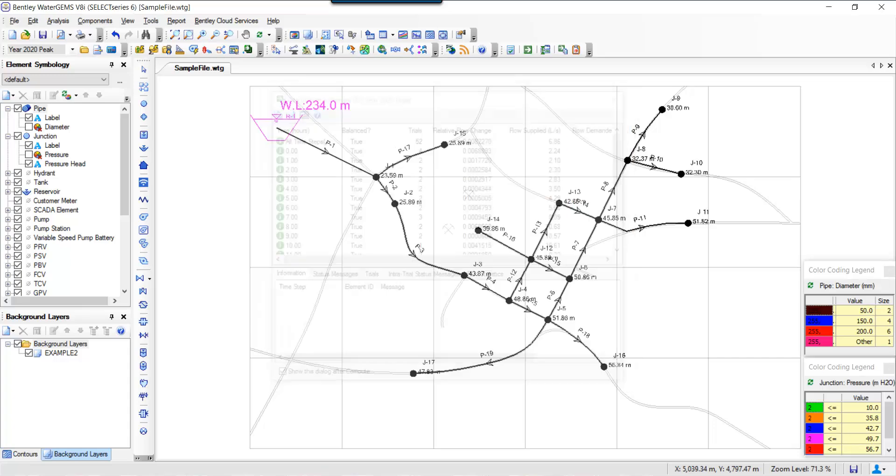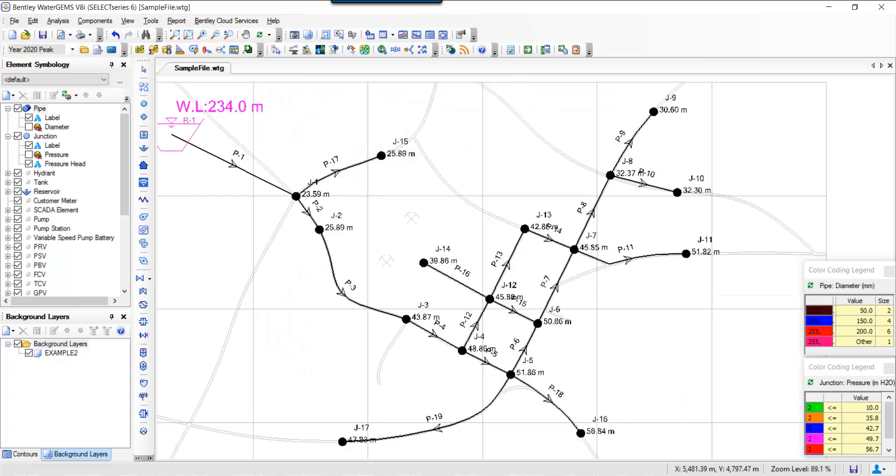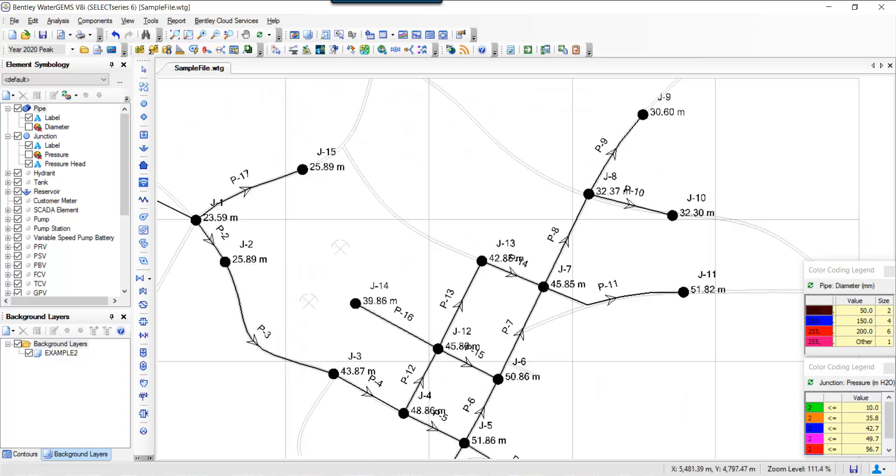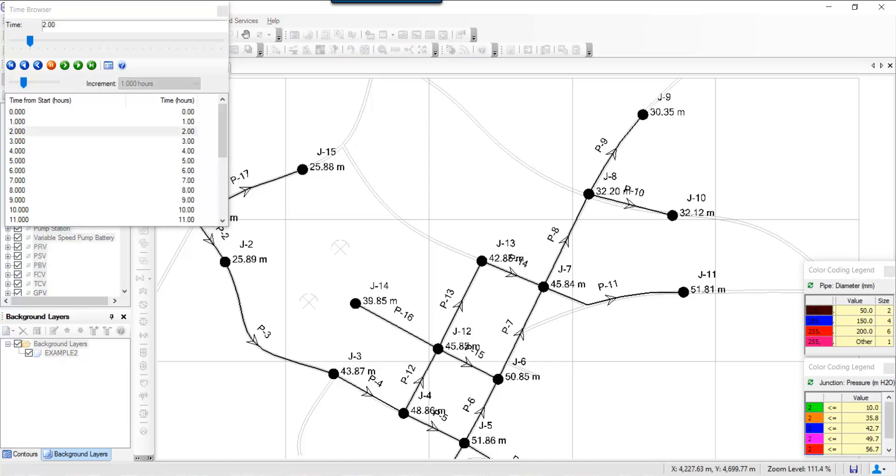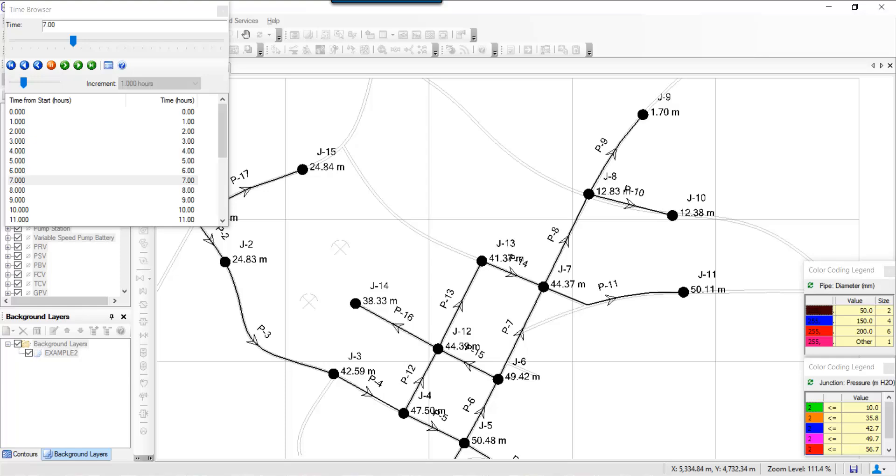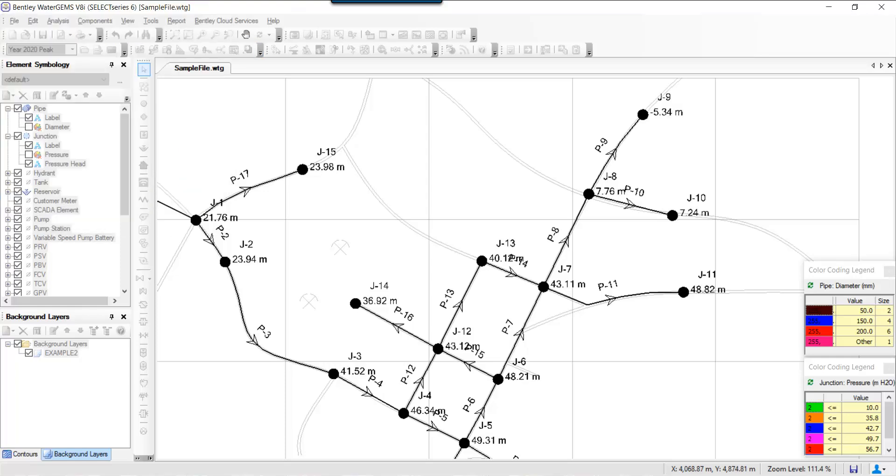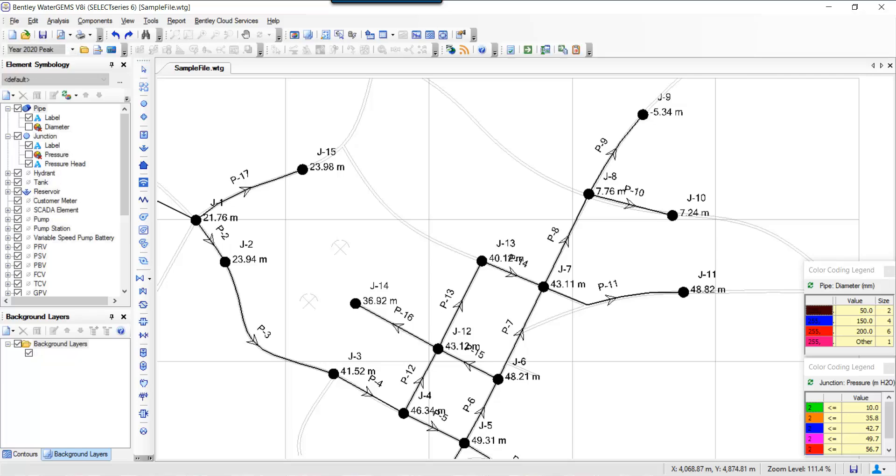30.6 meters. But as you look at the time browser, the pressure keeps on coming down, and at seven o'clock, eight o'clock in the morning, the pressures are really low because of high demands. So you can do a few things—you can actually improve your system.